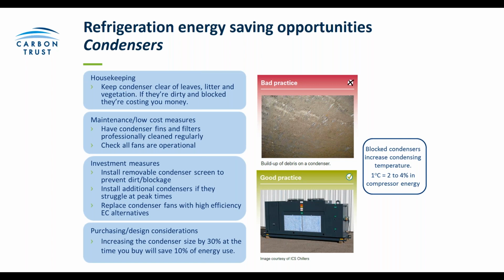In terms of maintenance and your low-cost measures, ensure that the condenser gets cleaned by a competent technician regularly, and make sure that during the process of cleaning that dirt isn't just pushed further into the fans, the fins that are used in the system. Check that the fans are all working. Remember that some may be switched off at times by the pressure controls, but just investigating whether they're all working gives you a good indication whether the system is working efficiently.